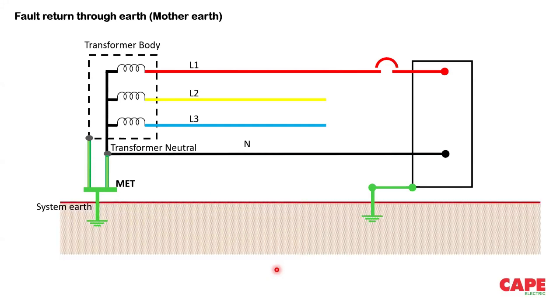Most of the time, our electrical installation is of this type. There is no metallic fault return path. We call it a TT system. The source is earthed separately. The source is connected to an earth electrode, and the equipment or the installation is connected to a separate earth electrode. Please note that in order to achieve a TT network, both these earth electrodes shall be electrically independent. Independent in the sense that these two must be at a certain distance, so that in case of a fault current flowing through one of the electrodes, the voltage gradient created shall not influence the other one. So, electrically independent earth electrodes. This kind of network is called a TT network.